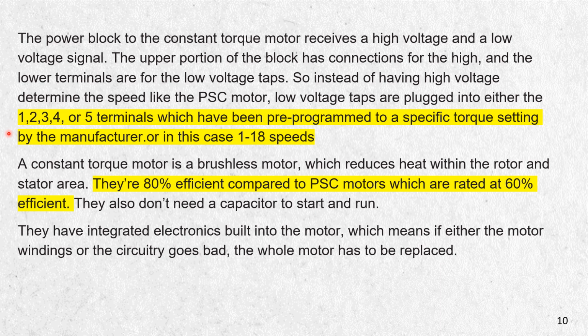And if you look at these numbers, on a lot of your Temp Star, you'll see speed taps 1, 2, 3, 4, and 5. 1 is low, 2 is medium, 3 and 4 are the same RPM. 3 is high for AC, 4 is high in heat, and usually ICP wants that 4 tap to always be with heat. And then you have a 5 pin, which is your high static pin for your AC for issues where you have ductwork issues, or too small a return, or ductwork not sized right, or deadheads or whatever. And in this case with this furnace, they're giving us 18 speeds to overcome the bad duct design and to generate enough airflow through that. With 18 speeds, I believe they're in like 60 CFM increments, so you'll be able to really dial in how much CFM you actually need for the particular job. So these new constant torque motors are now 80% efficient compared to the old ones that were 60%.